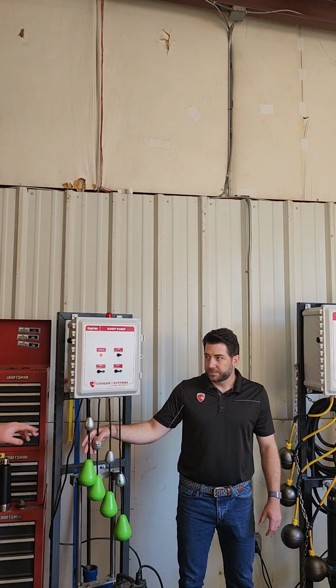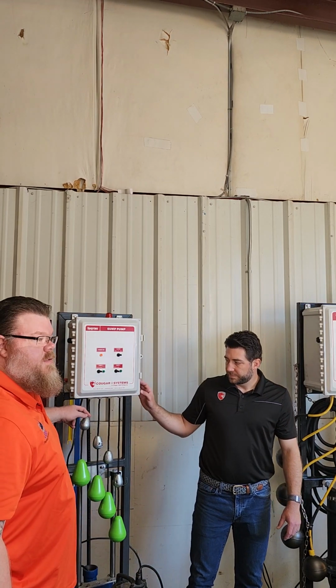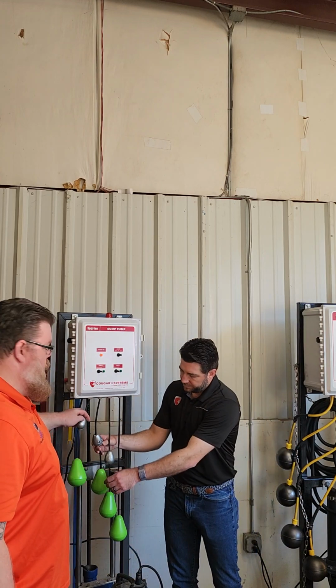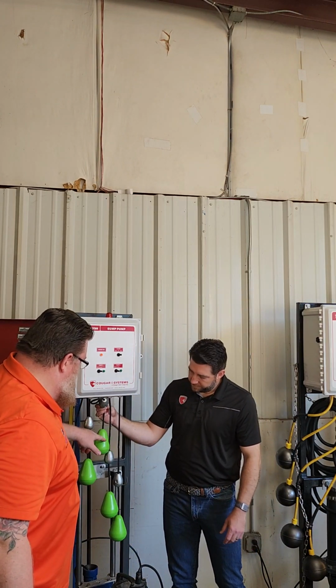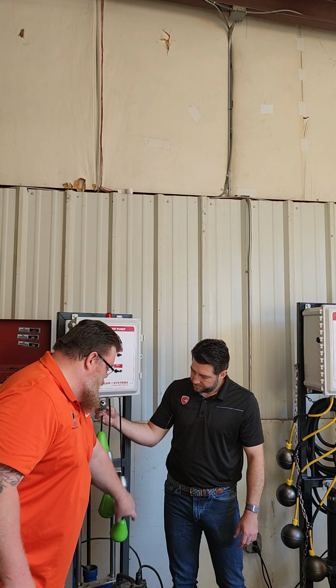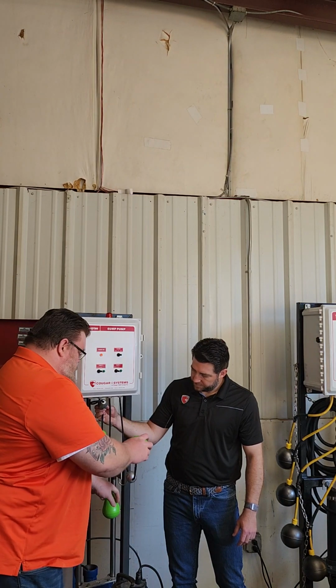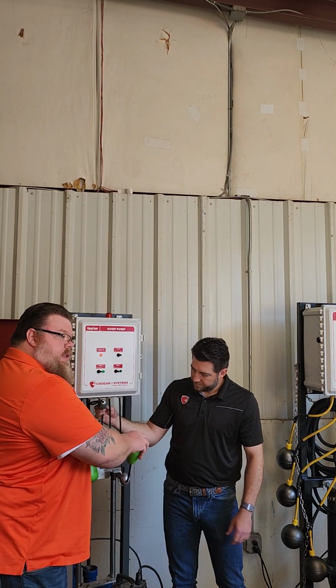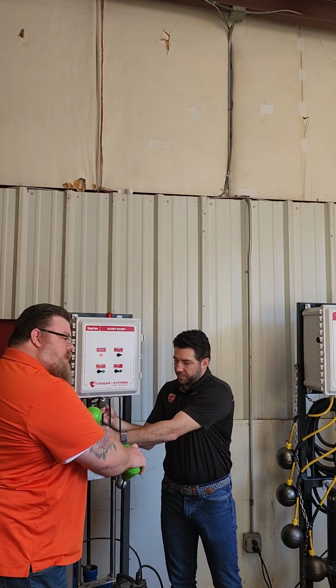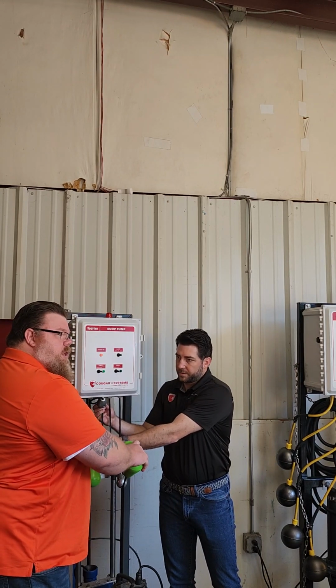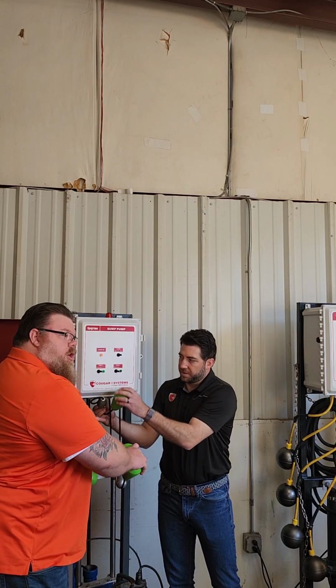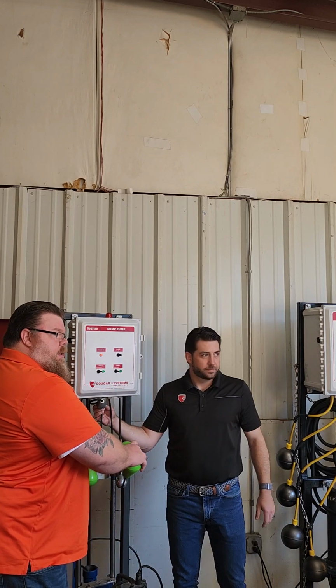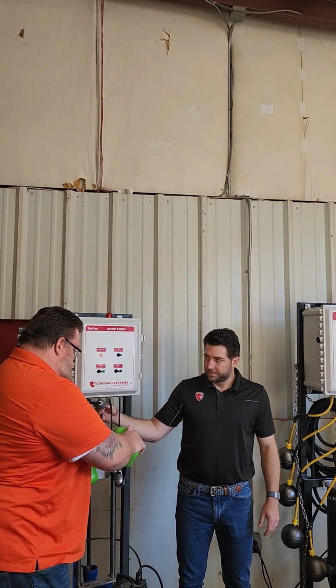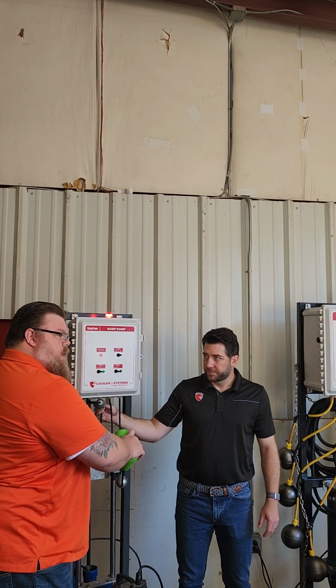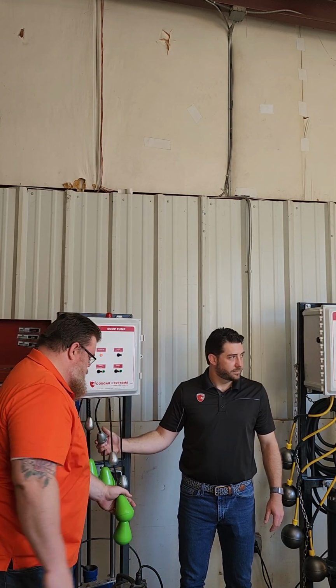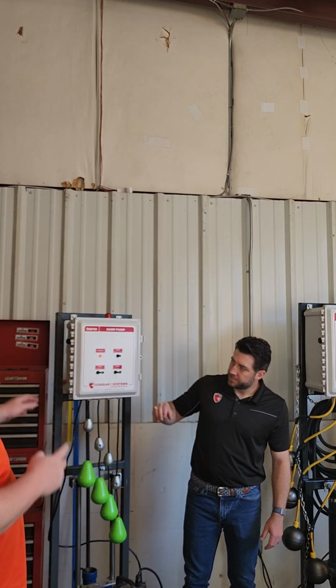So to be a little clearer, you would adjust this float differently, right? So if you want this float, this is your pump 2 here, this is activated on, this one's coming on, right? There's your second stage, second step there, and then you set this one lower so that this one will activate before your pump 2 comes on, right? So it's on, pump 1, alarm, and pump 2. So then, doing it like that, it won't piggyback each other then, right?